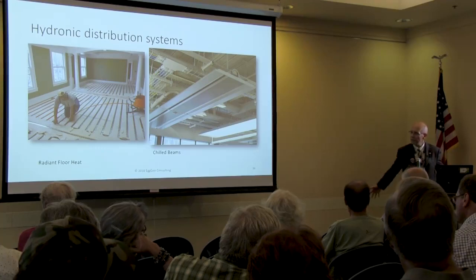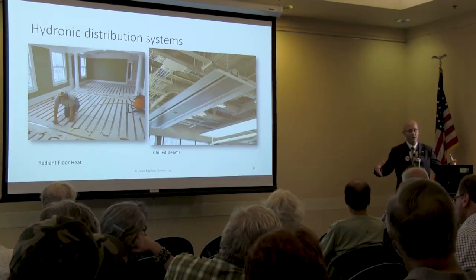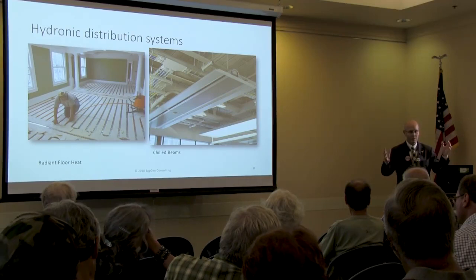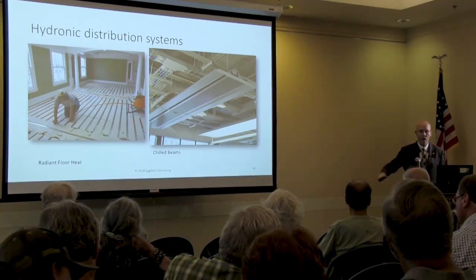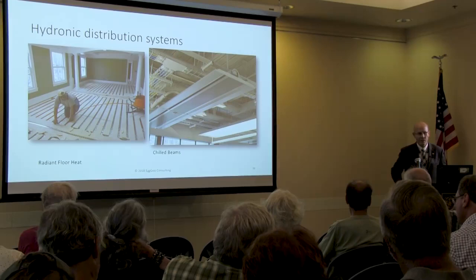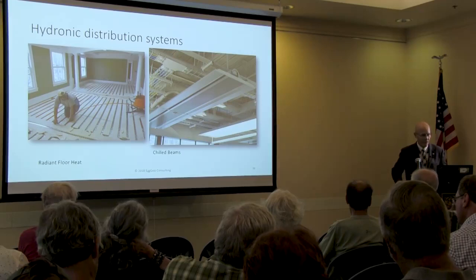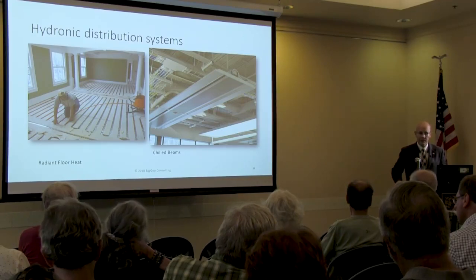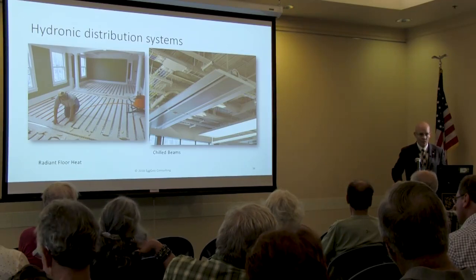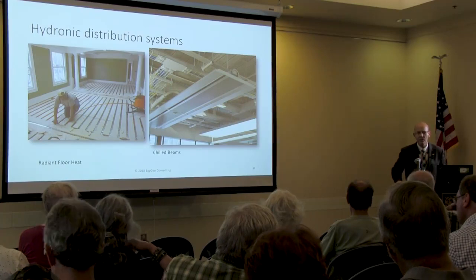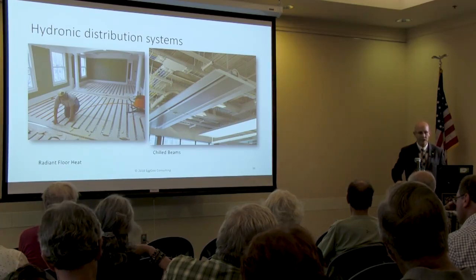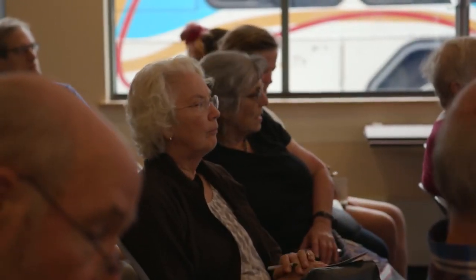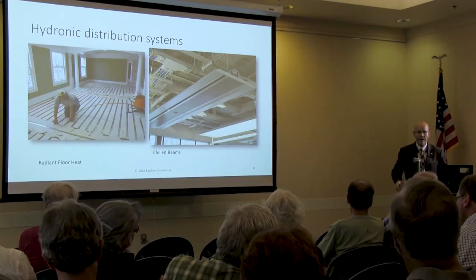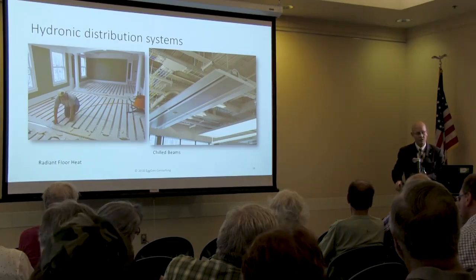Drammen, Norway had a district system that did all of the downtown buildings, 250 commercial buildings plus 60,000 residents, all hot. But they were using 180 degree hot water from natural gas fired boilers. They were able to get a chiller energy plant using the river water, which is at 40 degrees. It produces 195 degree water at a COP of 3.1. So when you get into the high end, the company is called Star Refrigeration.